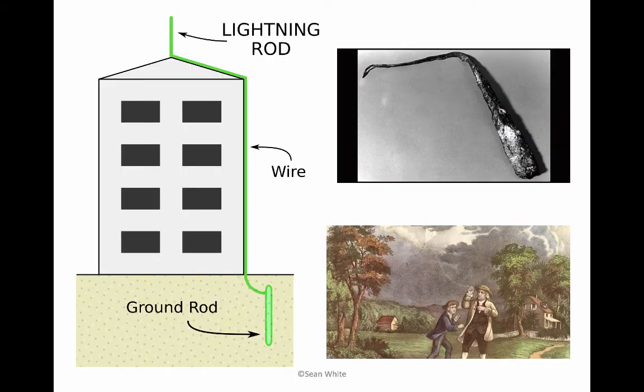And here's a little bit about what lightning protection is. We can see on this image on the left, right here, there's a lightning rod. And so it's going to capture that lightning and bring it down to earth instead of going through your electrical system. So let's think about what would happen if we instead connected this lightning rod to our PV system ground coming down there. Then all of a sudden we'd have lightning go through our PV system. So this is a separate deal, where it's bringing that lightning down to earth without bringing it through our PV system.